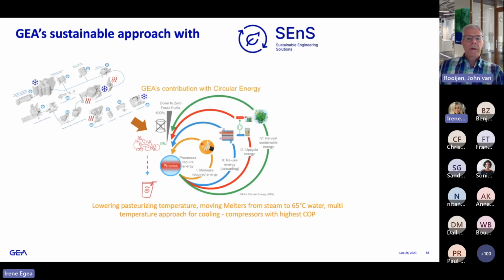We also, from the GEA side, supported the company who provided the melters to step away from steam and do the melting of the product with hot water of 65 degrees. On the cooling side, we implemented a multi-temperature approach for cooling. So by applying different temperature levels, the COP of the total solution is also increasing. And we also applied state-of-the-art piston compressors to reach the highest COP level for these kinds of applications. Please forward.